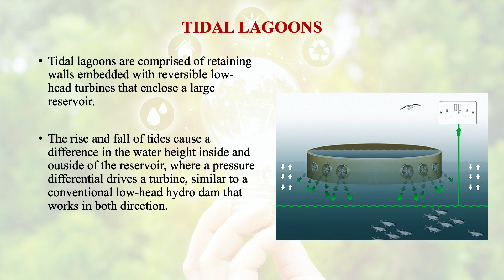As we know, tidal lagoons are also used, water lagoons. Lagoons are comprised of retaining walls that are embedded with reversible low head turbines that enclose a large reservoir. The rise and fall of tides cause a difference in the water height. Suppose this is rise and this is fall, then there is a considerable difference between the water height inside and outside of the reservoir. Then what happens? A pressure differential is there which drives the turbine. The concept is similar to a conventional low head hydroelectric power generating dam that works in both directions.